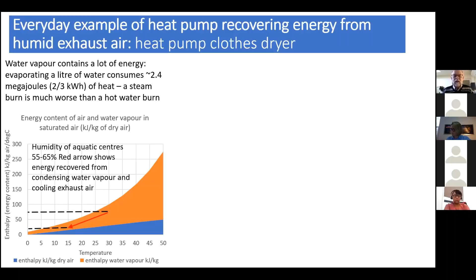So when we look at the exhaust air coming out of the pool, in many cases it's not used very effectively. It may just be pumped out of the building, or you may try to recover some heat with a heat exchanger. But a heat pump can condense the water vapor in that air and extract a large amount of energy while it cools the air and condenses the water.